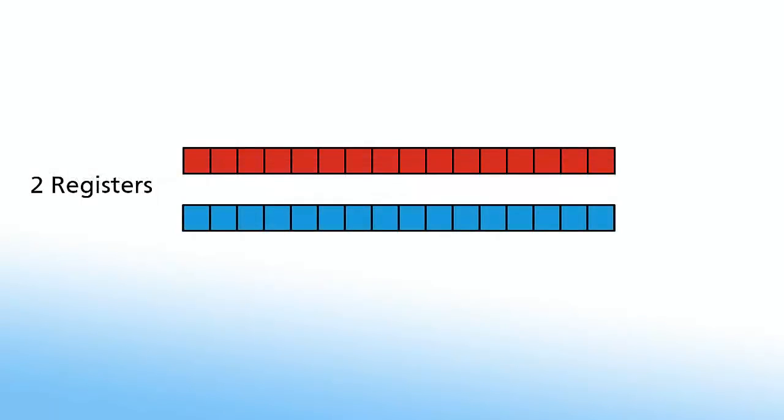Modbus as a protocol does not define exactly how the data should be stored in registers. Different vendors have different ways of storing and transmitting data. Some devices will transmit the higher byte first, followed by the lower byte. Others will do it the other way around. By the same token, when registers are combined to represent 32-bit real values, some devices will transmit the higher 16 bits in the first register and the lower 16 bits in the second register. Other vendors do it the other way around.